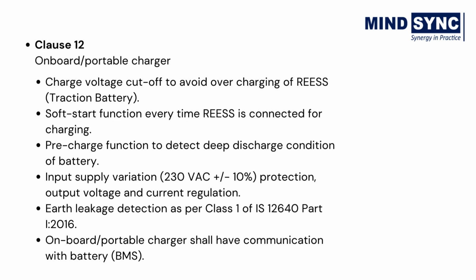The portable charger shall have charge voltage cutoff to avoid overcharging, soft start function every time the battery is connected for charging, pre-charge function to detect deep discharge condition, input supply variation protection, and earth leakage detection. Charger shall have communication with battery.